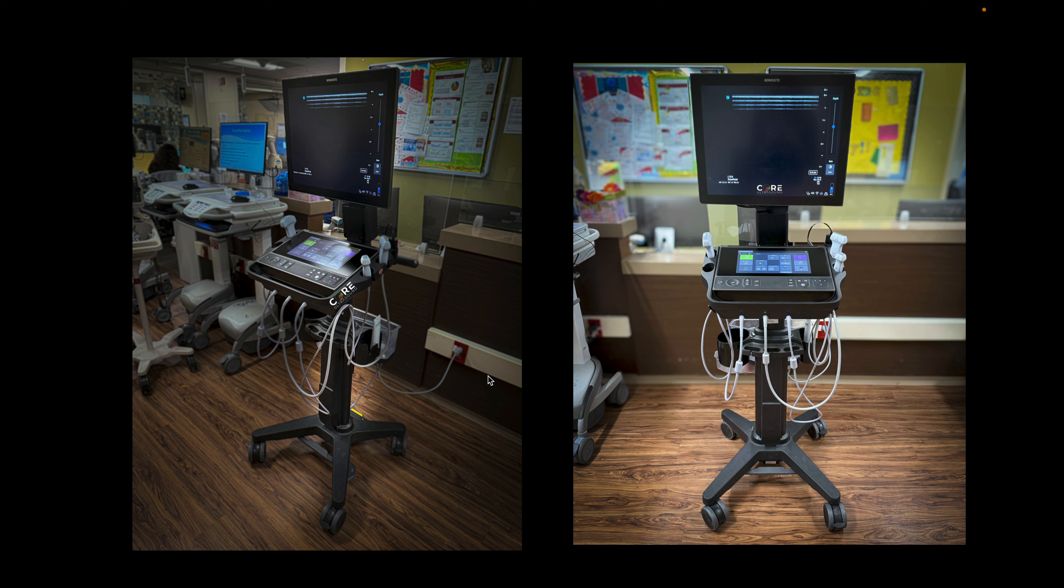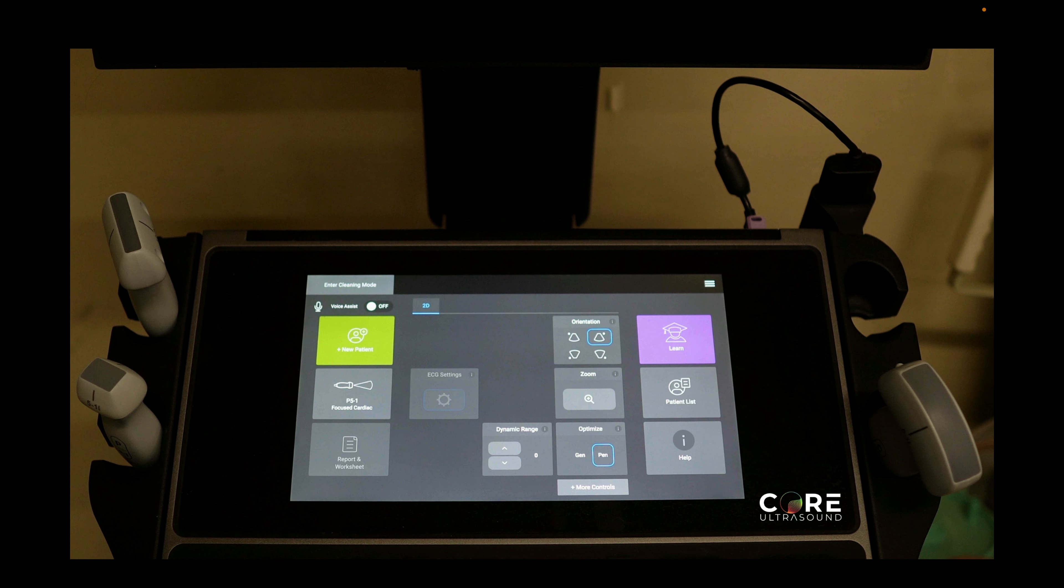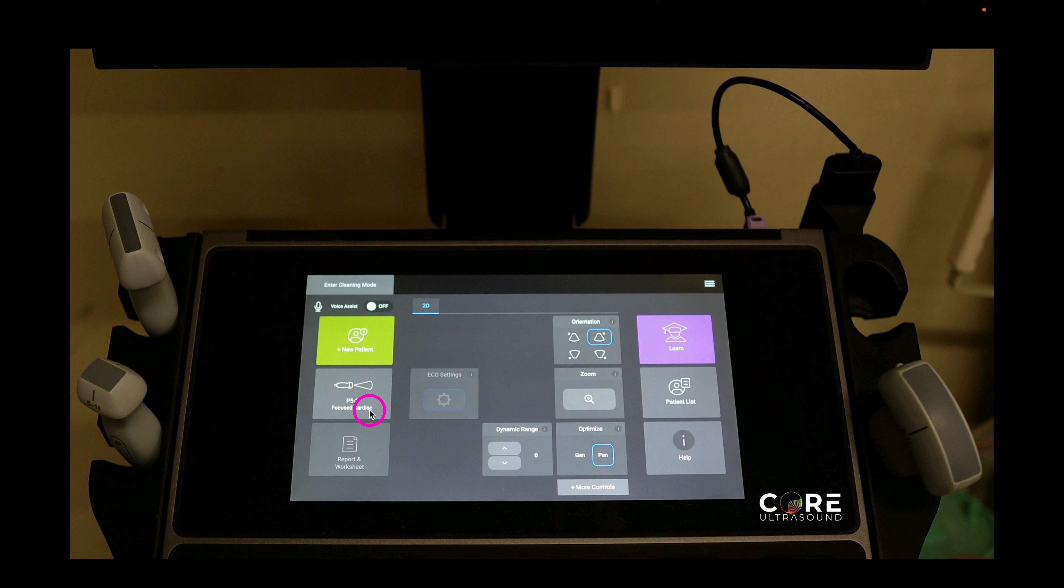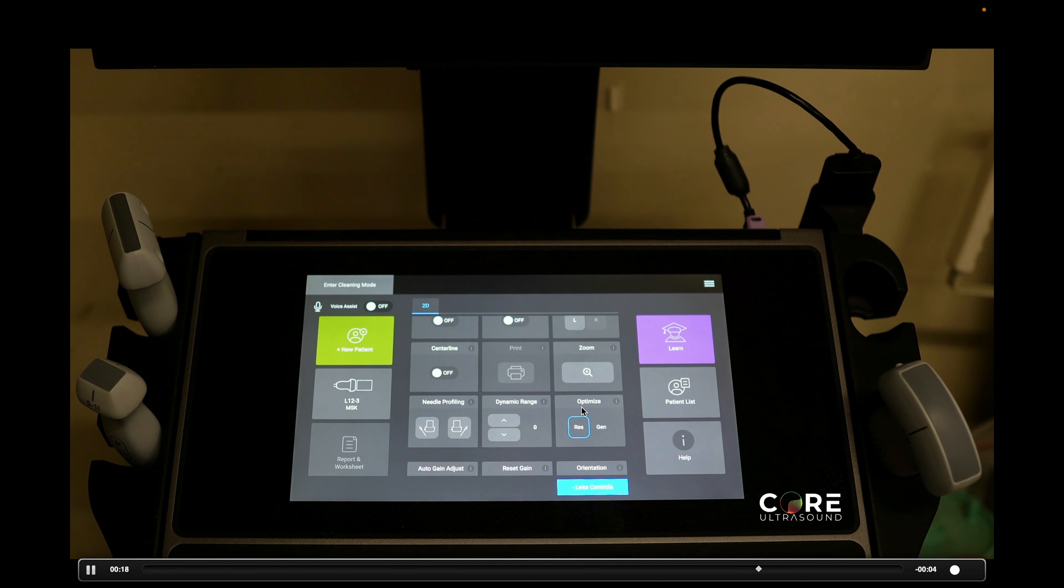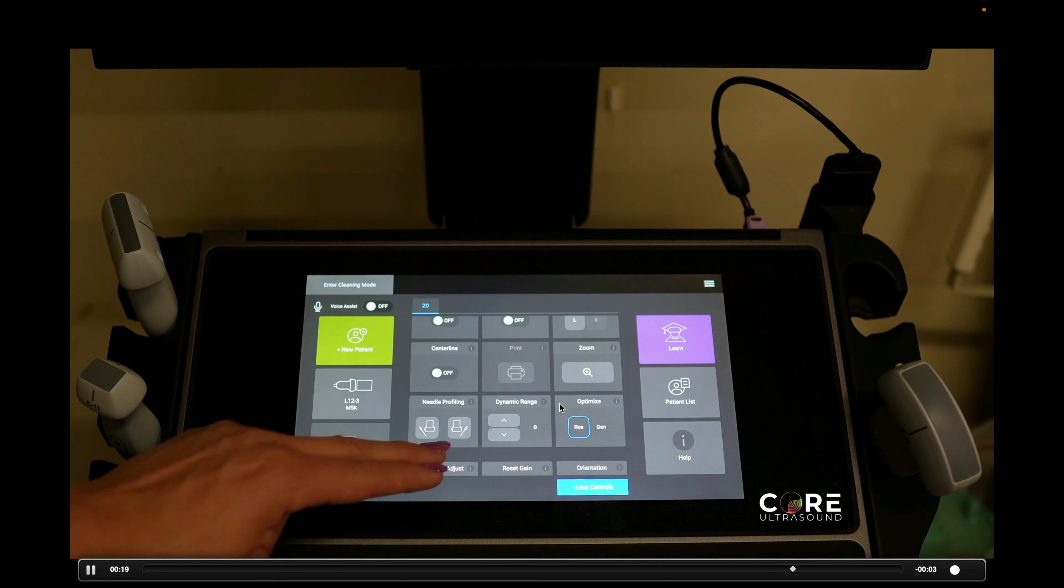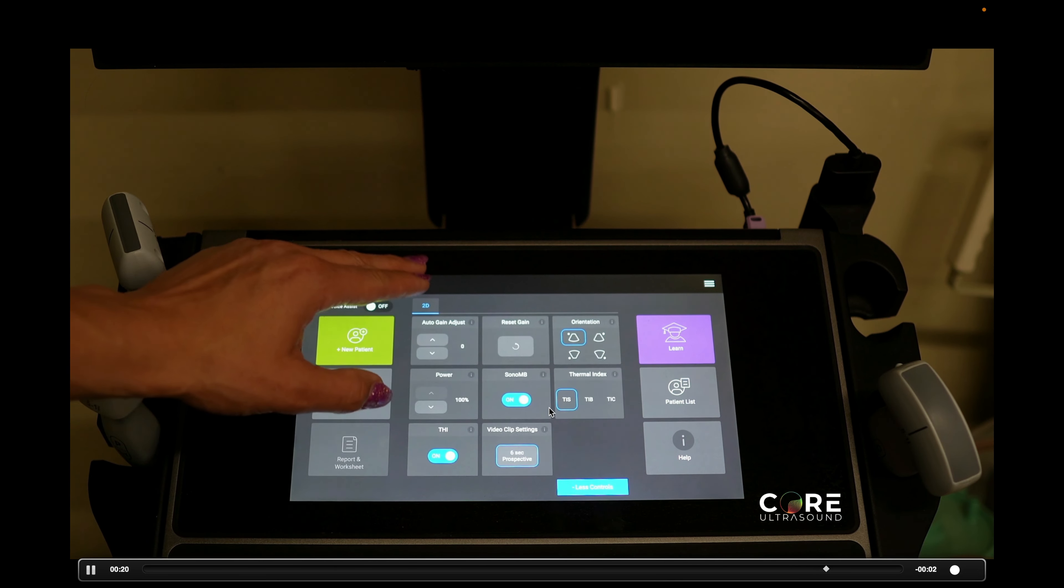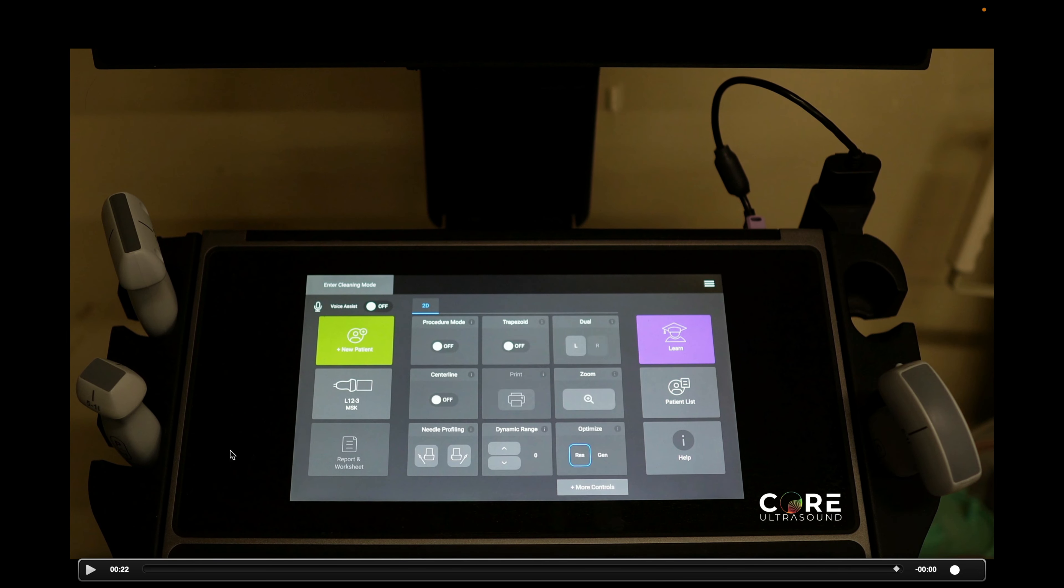Let's now talk about how to select a transducer. So this is the bottom part of the screen, the touchscreen part. And if you notice right here, we have the phased array transducer. That's this one right here that is selected and it's using the focused cardiac setting. This is something that we can change. We hit this button here and we can select whatever transducer we want, as long as it's connected physically underneath to the module here so that we can access that probe. We can do some fine tuning on how the probe works, but this is all kind of extra. You can just select the transducer and the exam you want and start scanning.